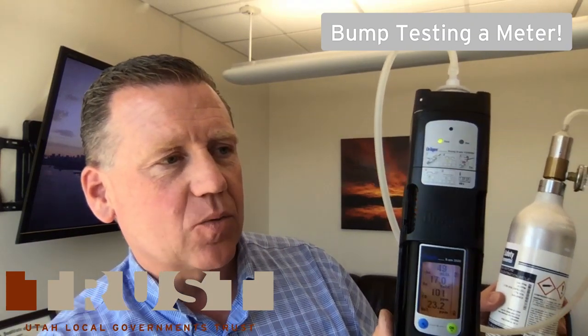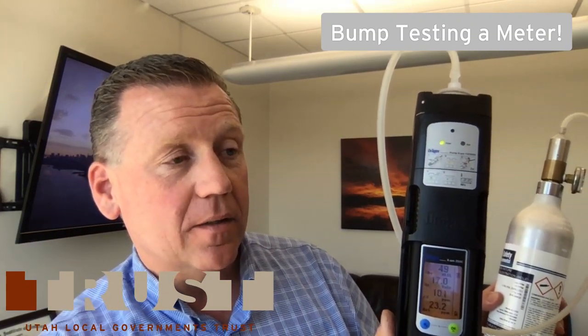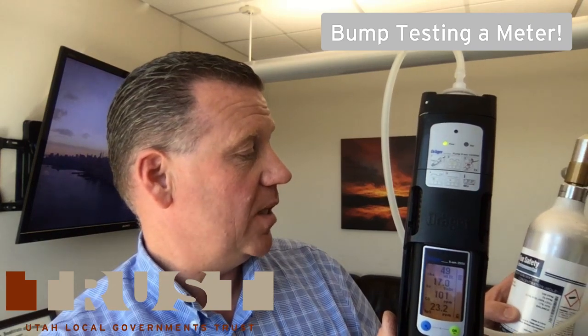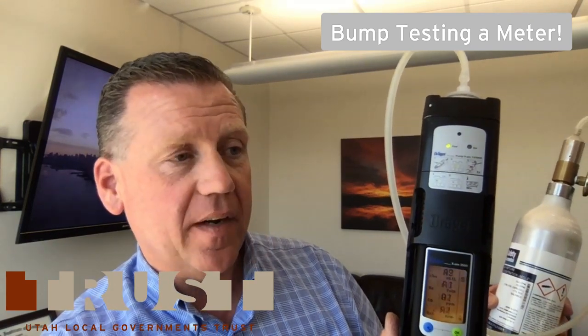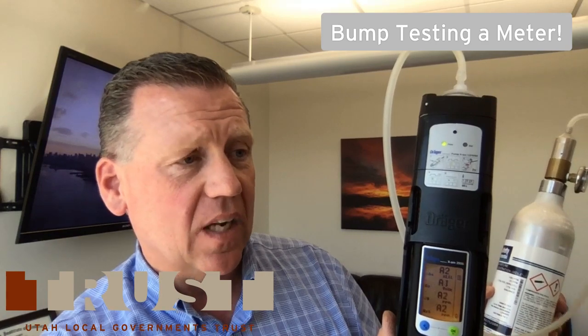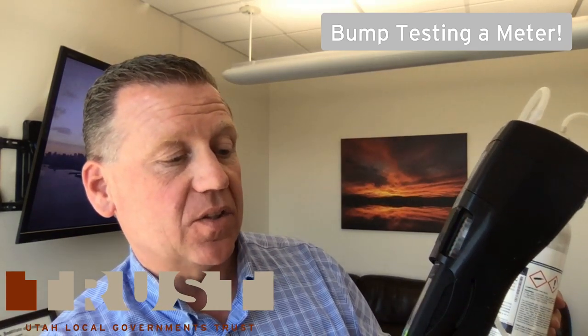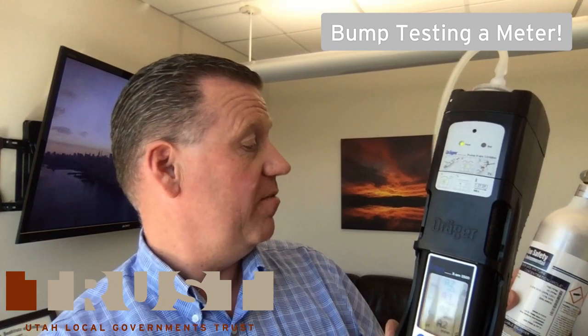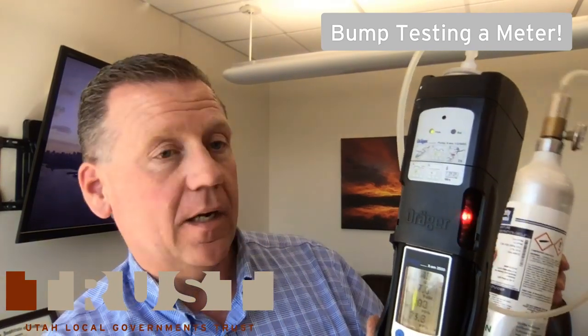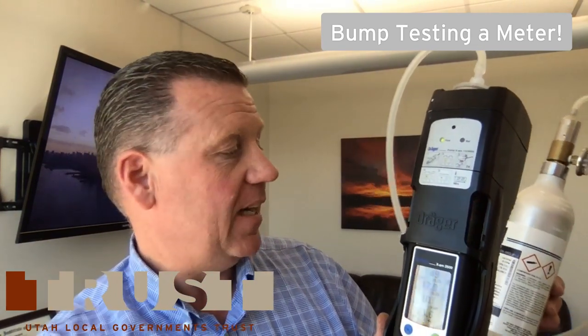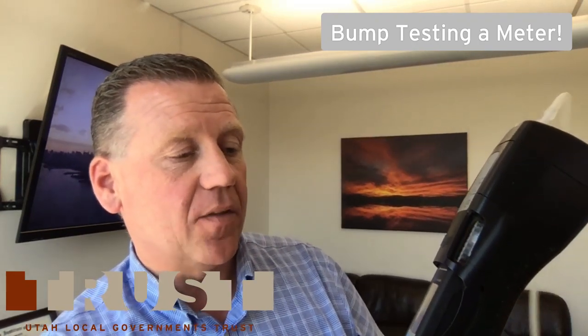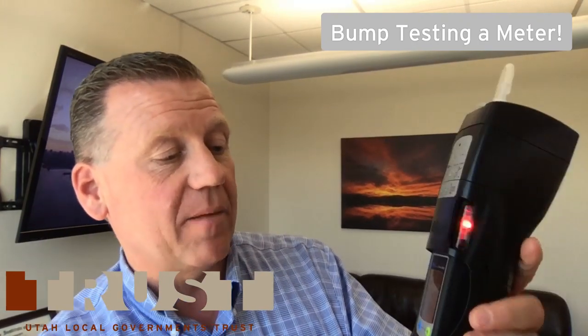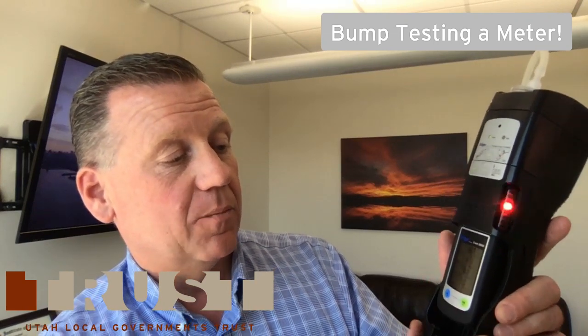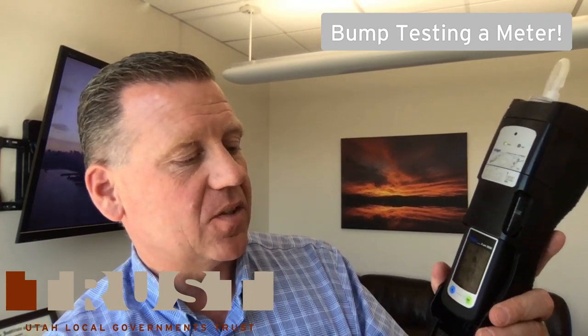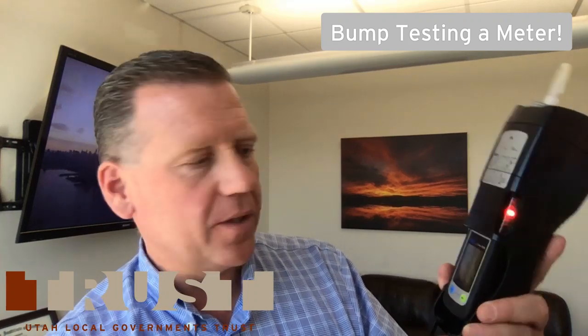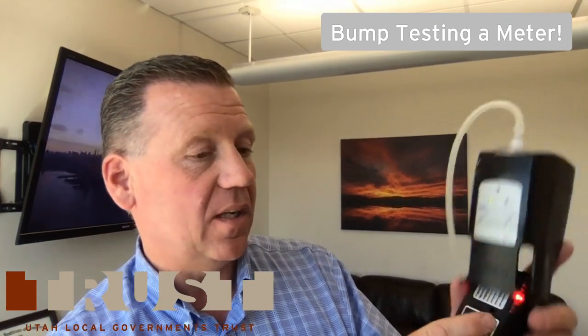The next one I'm looking at is 101 parts per million, and that's for carbon monoxide. And it says 100 there. Okay, we're within tolerances. And that last one is hydrogen sulfide. It's reading 23.4. And on my bottle, it says 25. Now, I'm enough out there on that one. I'm going to let it stabilize here for a minute. But I'm more than a part per million out on that hydrogen sulfide. That's pretty serious. I'm going to turn this off.